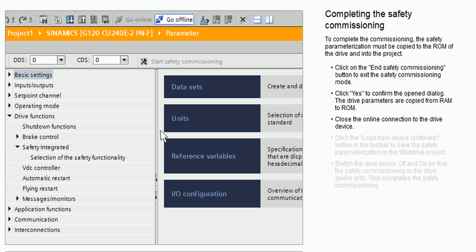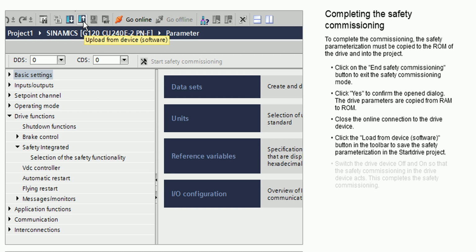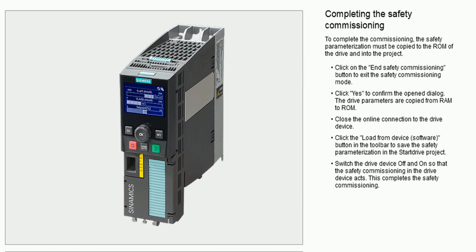Close the online connection to the drive device. Click the Load from Device, Software button in the toolbar to save the safety parameterization in the Startdrive project. Switch the drive device off and on so that the safety commissioning in the drive device acts. This completes the safety commissioning.